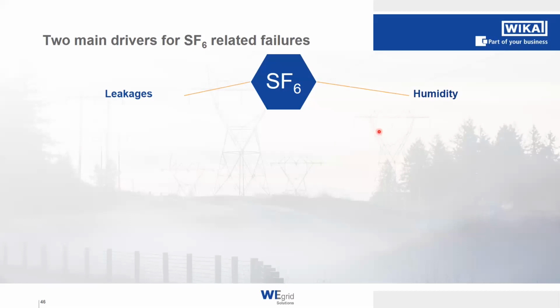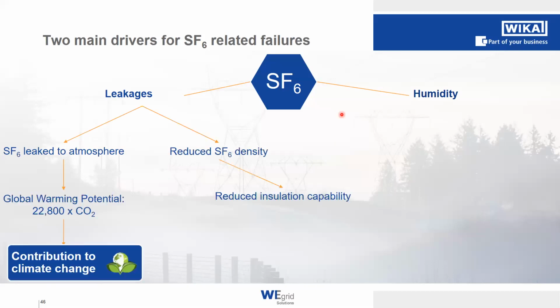Exactly. So leakages in SF6 gas compartments mean that SF6 is being leaked into the atmosphere. And this is contributing to global warming, as Florian already said, because SF6 has a global warming potential of 22,800 times the potential of CO2. That means if 1 kilogram of SF6 is emitted into the atmosphere, this equals the same amount of 22.8 tons of CO2. So this is a huge factor that we always have to keep in mind when handling SF6 gas.